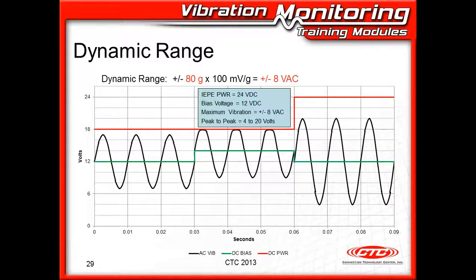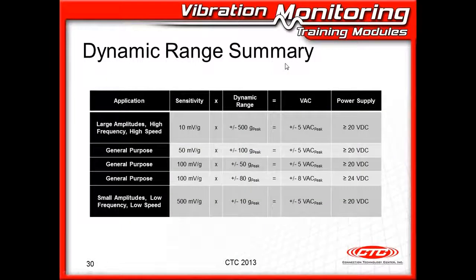So recognize that you can clip a signal because your power supply voltage is too low, and we don't really want to get in that position. So on this chart, based on the sensitivity of our sensors here, times the dynamic range that they produce, and the voltage output for the vibration, I've listed the power supply, and you should have these equal or greater than the listing here. So I would always like to see a power supply that's greater than or equal to 20 volts DC. And if I've got one of these 80G sensors, well, now I need to have something that's greater than or equal to 24 volts DC. So I don't want to clip because I'm limiting the power supply.